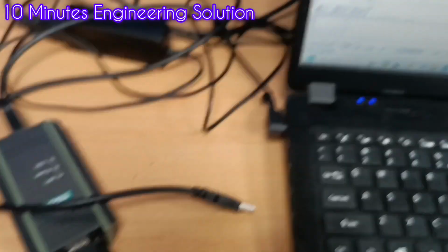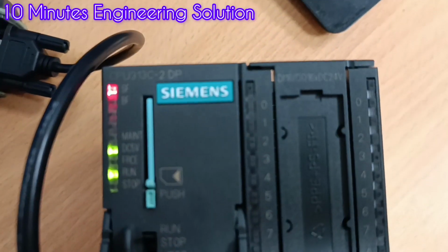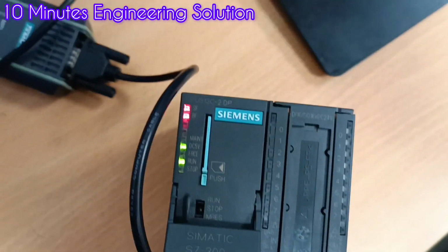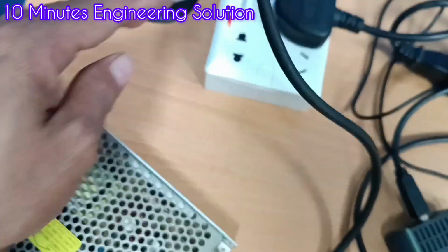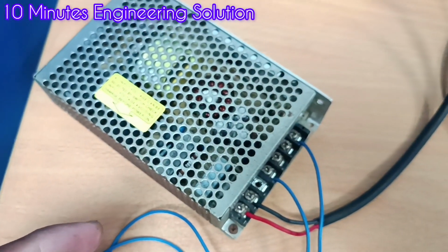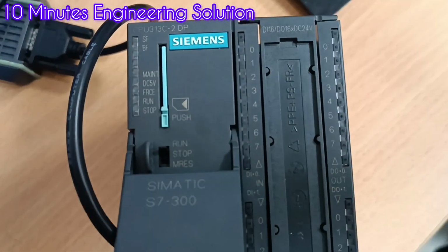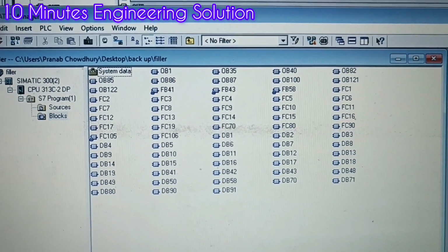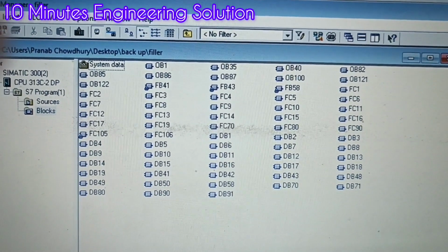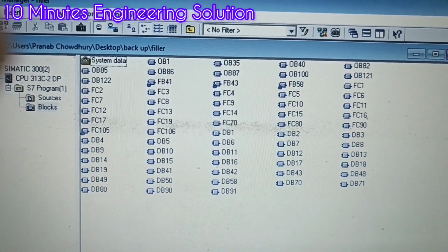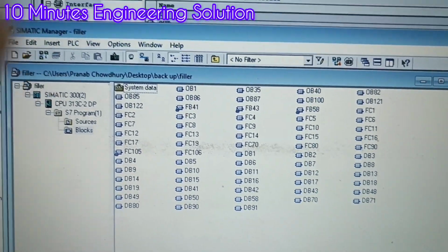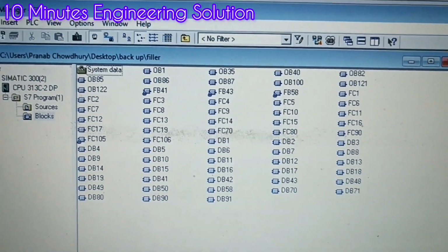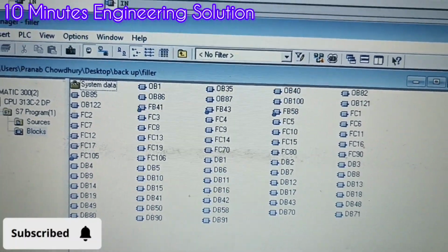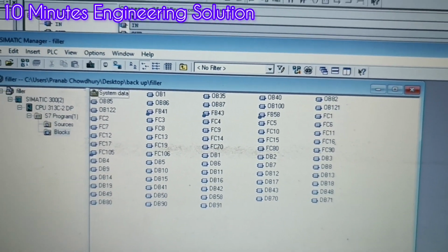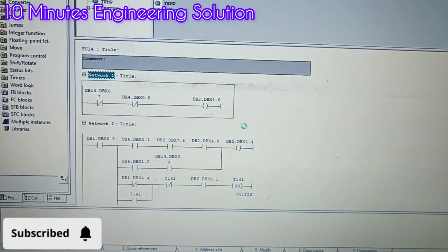Okay, now if you want to open the system, no problem. You can upload the full program. Now there is no need for the MPI cable connection. You can see it is totally disconnected now, from the CPU to laptop. Now we can stop the power for the CPU. The power supply is also off and the CPU is also off because your program is already uploaded from the PLC to PC. You can see the picture, all the blocks in here. You can see individual power blocks in here, all the simulation blocks in there. OB1 is the main program, where all the programming is combined. When you need to edit or modify anything, you can modify and edit it, and when you open OB1, all the programming is included in here.